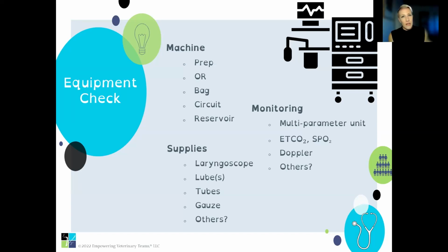You can work with a pediatric circle system. I prefer an F circuit. It's whatever you have in practice that you're comfortable with and have utilized, and make sure you check them for leaks. You want to ideally replace these at least once a year, if not twice. So you want to clean them out with soap and water. Don't use any chemical cleansers. Just Dawn dish soap is great. And make sure you rinse that really thoroughly and spin it around.